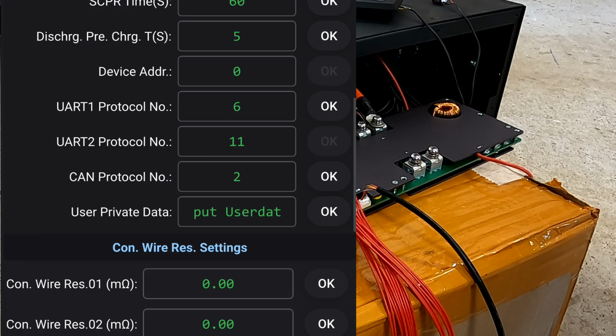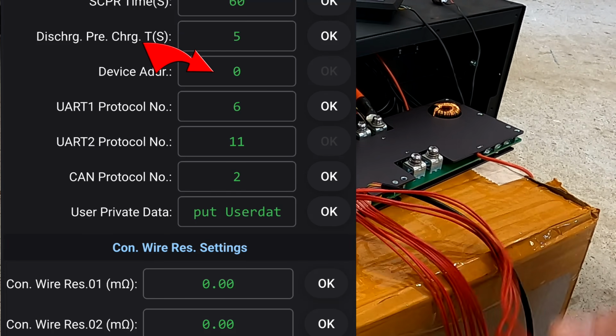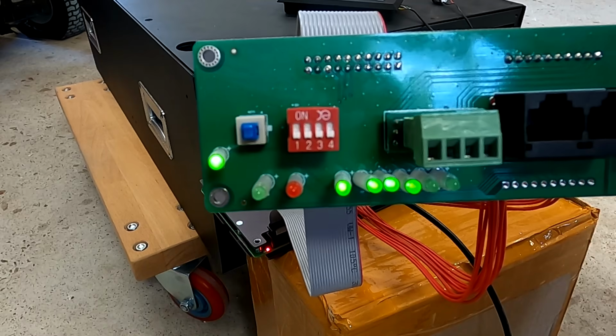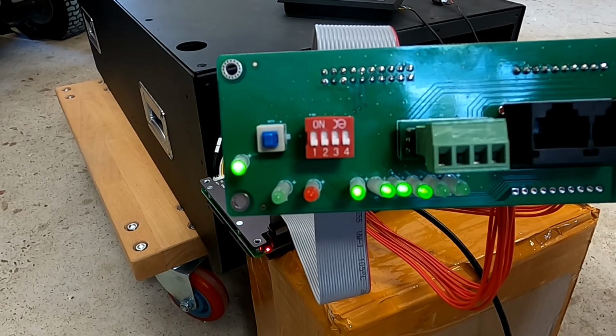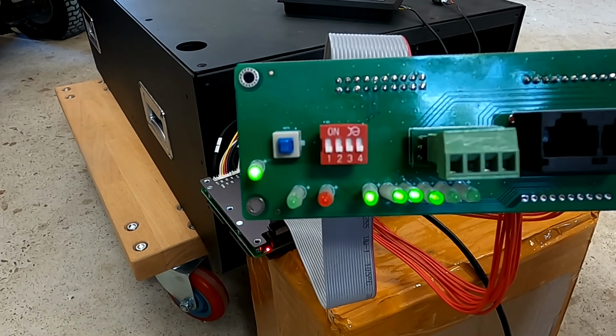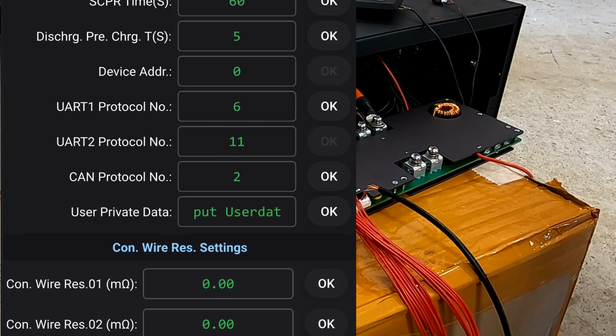Well, and then we have 4 new settings here, which we have not seen before. This is purely for the communication side of the BMS. We've got a device address, which sits at 0 at the moment. And this is exactly what we have here with our dip switches. So when I change the dip switches to something else, we have a different device address showing here in the app as well. Then we've got 2 UART protocols, UART1 and UART2.